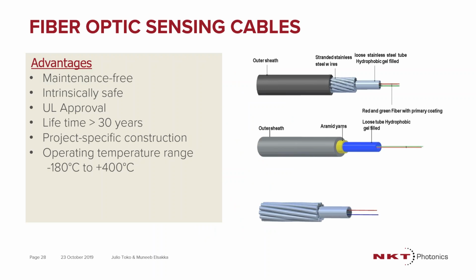You have multiple types, and we can do it based on the application. So for instance, we have a ruggedized stainless steel cable with the outer sheath. That's the picture on the top right. These are the type of cables that we use mostly for areas where we are worried about, let's say, electrical interference or such things, and areas where we know, for instance, that the contractor might not be familiar with fiber optic linear detection. So this purely looks like a wire. It's just as rigid, with high tensile strength and high crush resistance. One of the drawbacks is that when people hear fiber optic, they think it's weak, but this is the type of cable that is pretty much a wire.